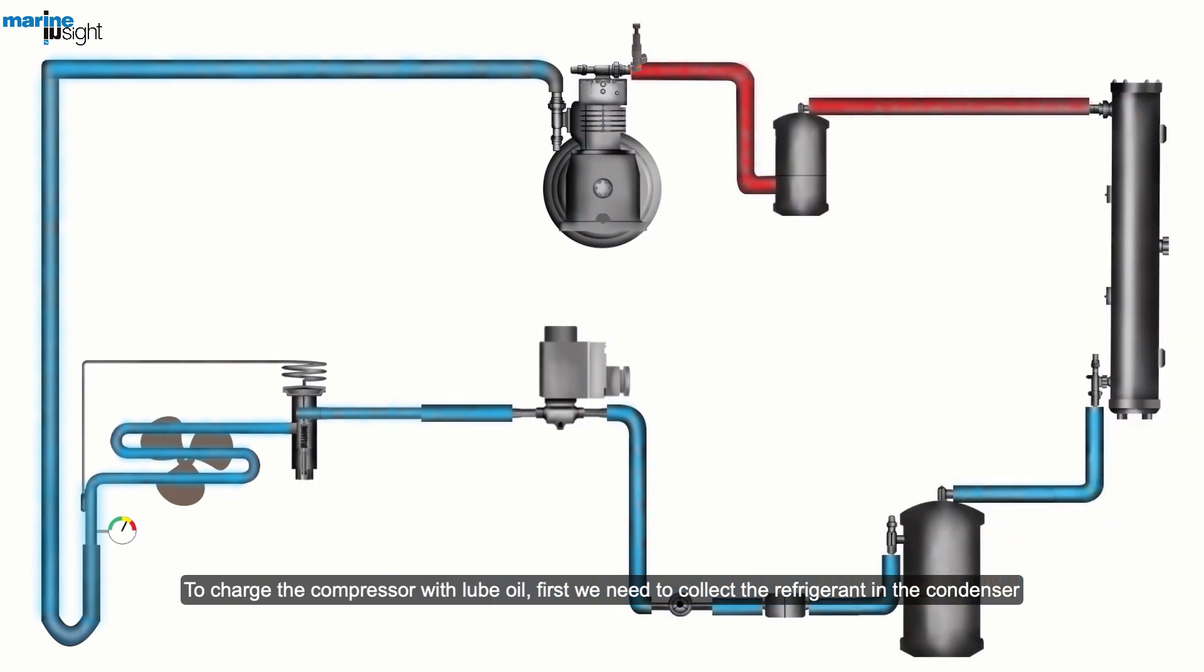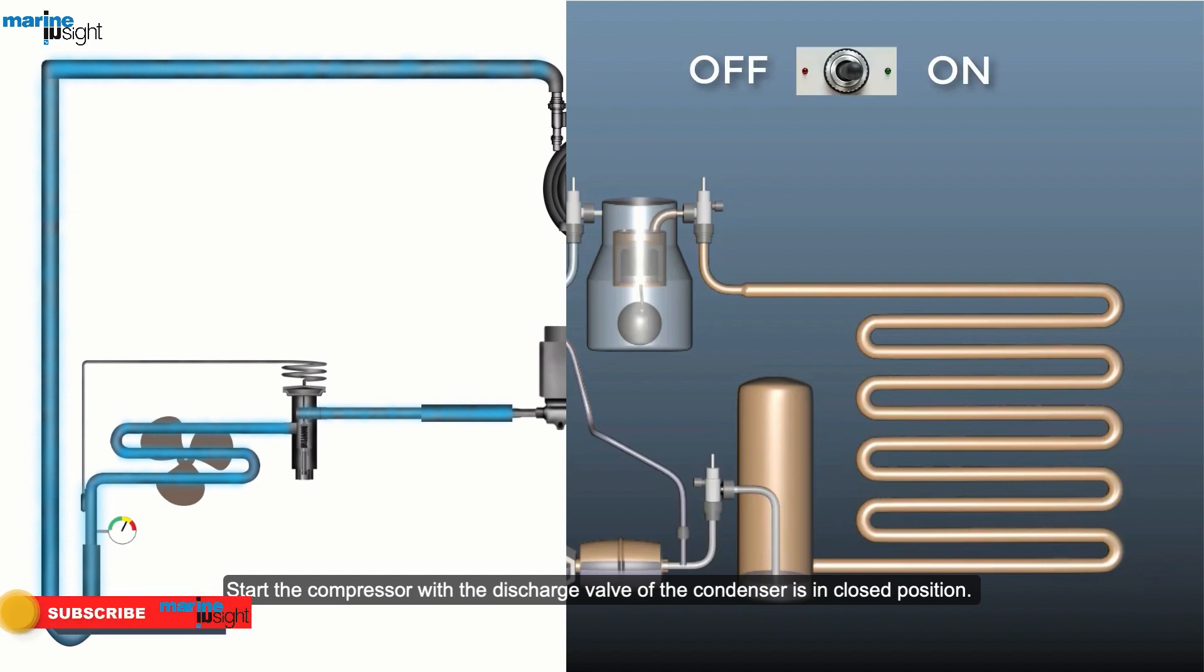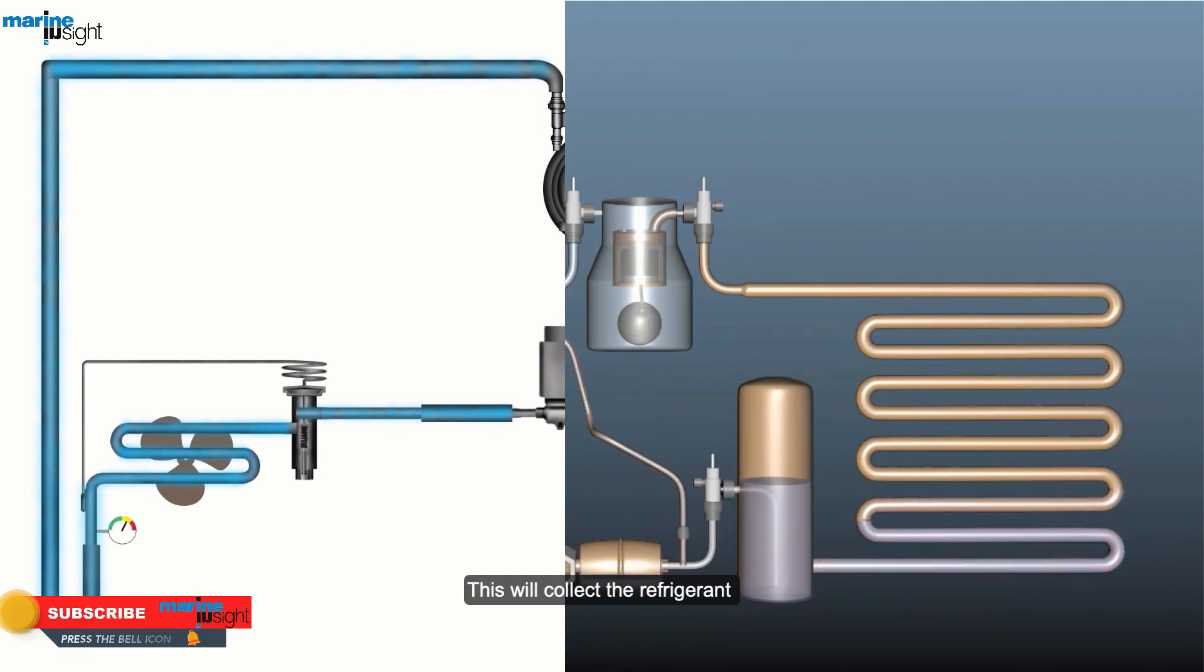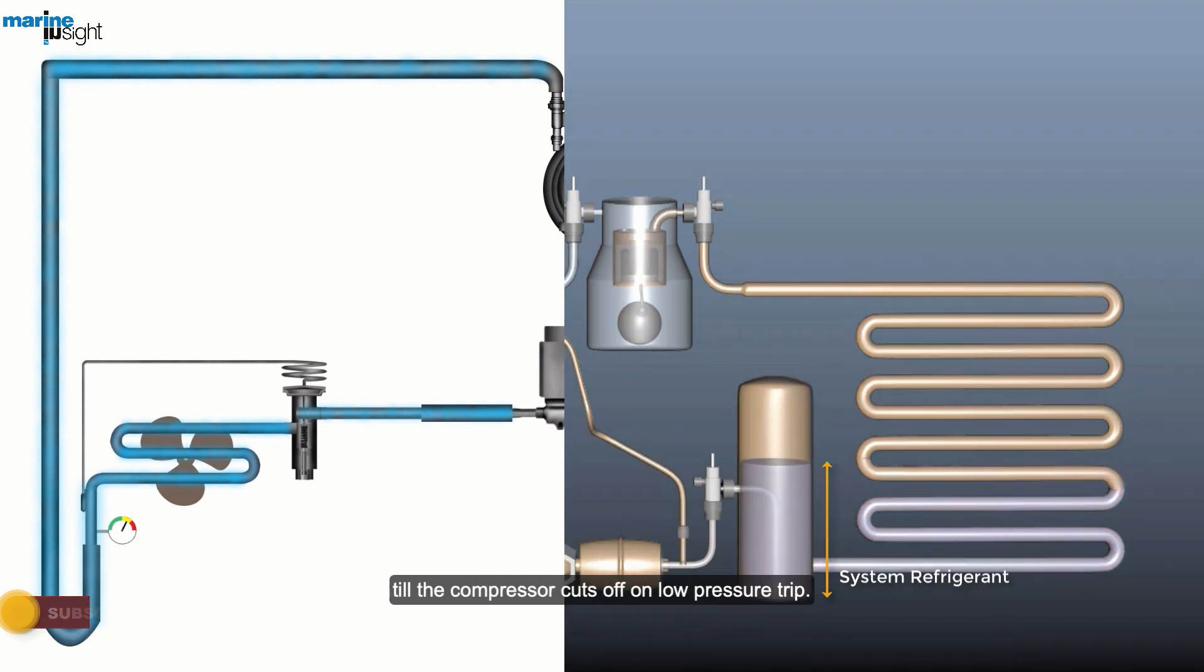To charge the compressor with lube oil, first we need to collect the refrigerant in the condenser. Start the compressor with the discharge valve of the condenser in closed position. This will collect the refrigerant till the compressor cuts off on low pressure trip.